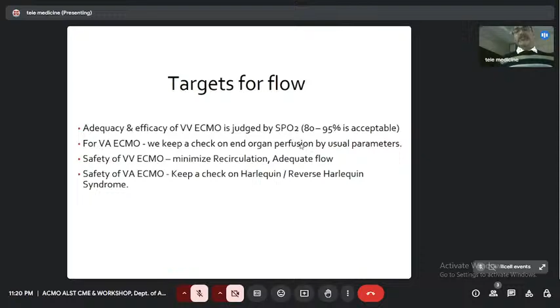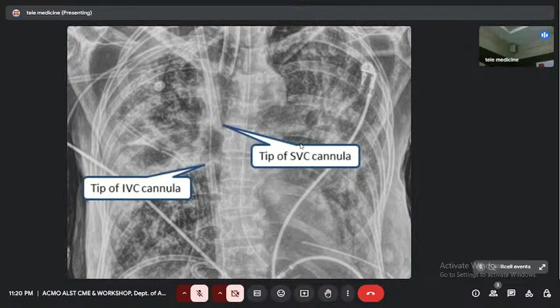But just remember, there's something called recirculation, because I'll just show you. There's something called recirculation where both the cannulas are in the major veins. So if you can see, this is the drainage, this is the return cannula, and this is the tip of the drainage. Both the cannulas should not be very near, because once that happens, the ECMO machine is just working in a loop. Whatever comes out in the drainage is actually returned by the return cannula, and it's not being delivered to the systemic circulation, but it's just flowing back into the drainage, and that's called recirculation. So we have to limit these things. We have to ensure there's an adequate gap, which is at least more than 10 centimeters.